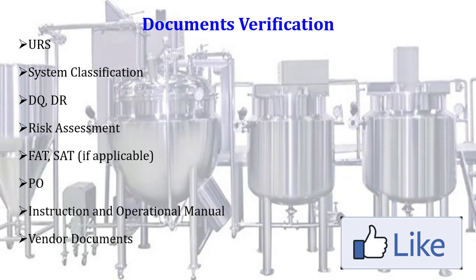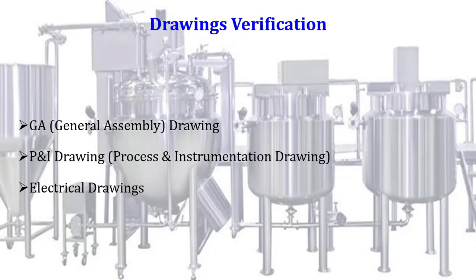Documents verification also includes purchase order verification, instruction and operational manual verification, vendor documents verification — which includes DQ, IQ, PQ documents and operation manual. In drawings verification, we generally verify GA — general assembly drawing — P&ID — process and instrumentation drawing — electrical drawings and other applicable drawings based on the design and type of equipment.